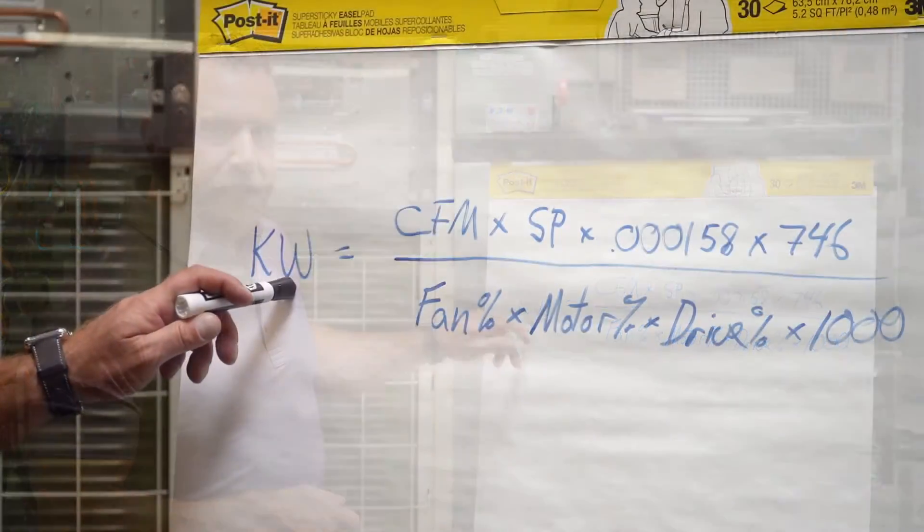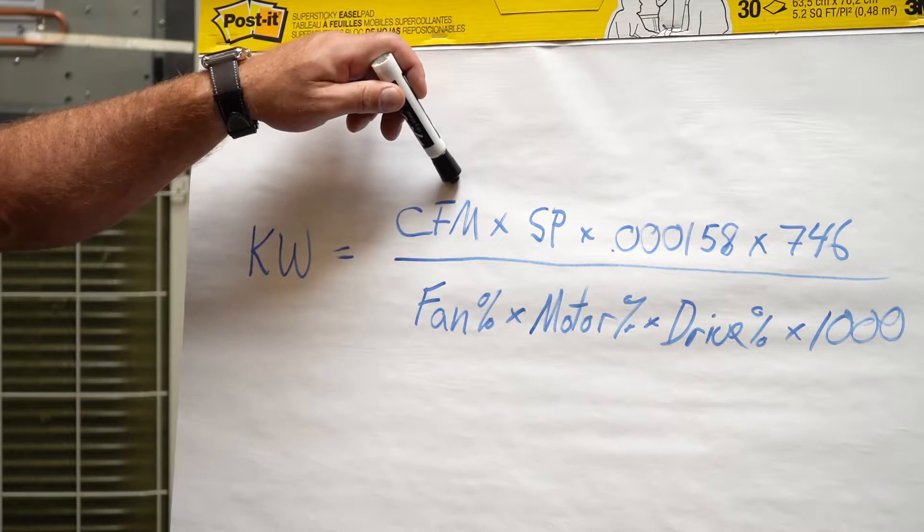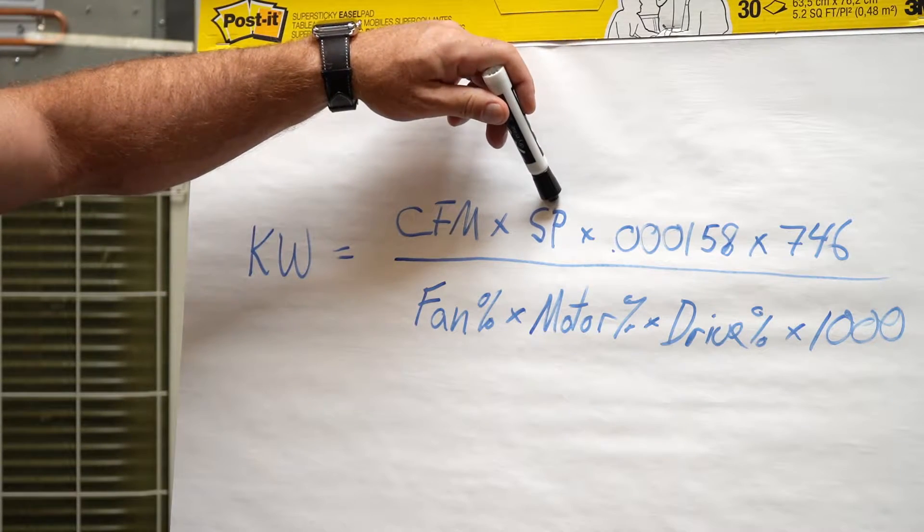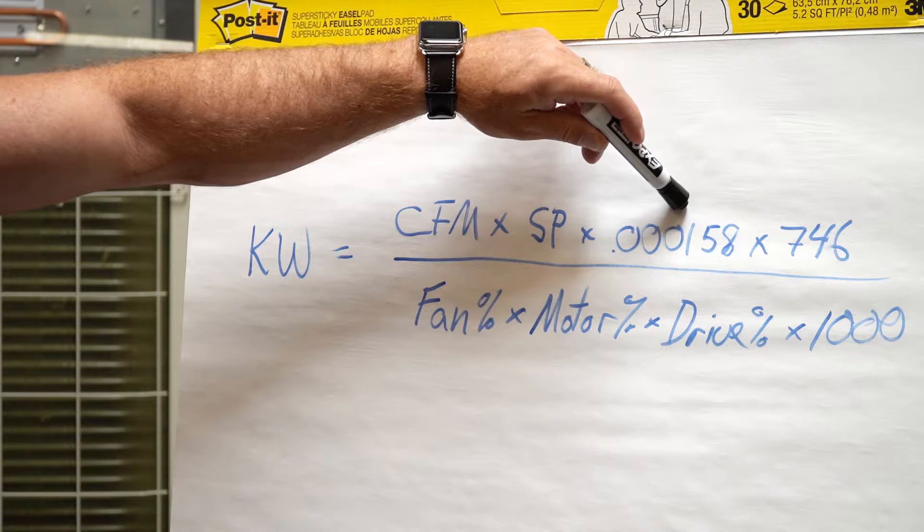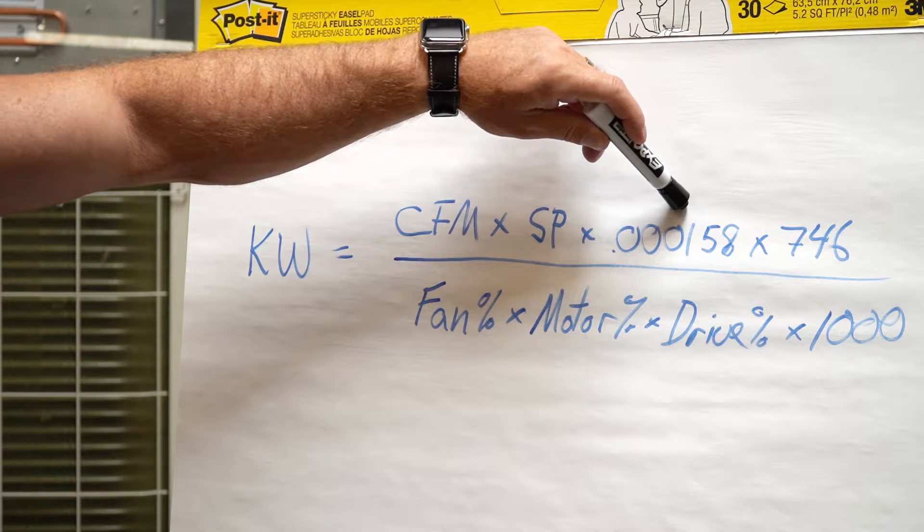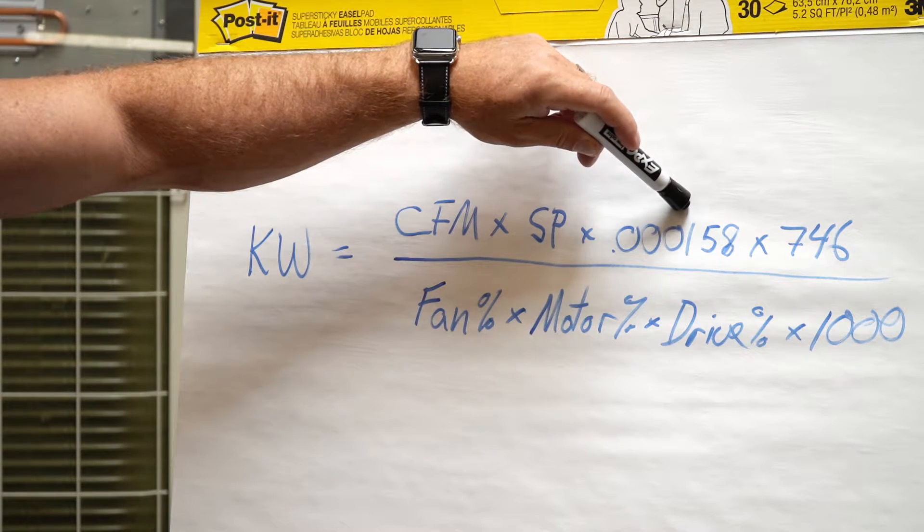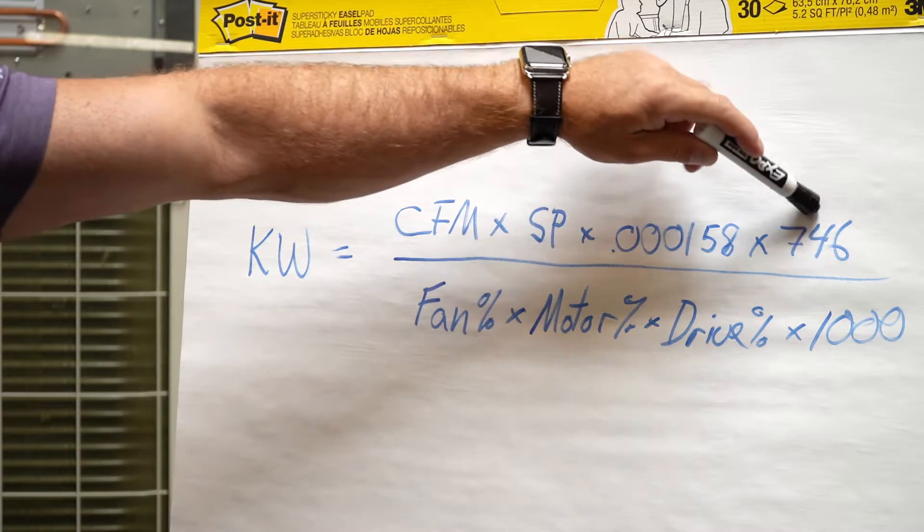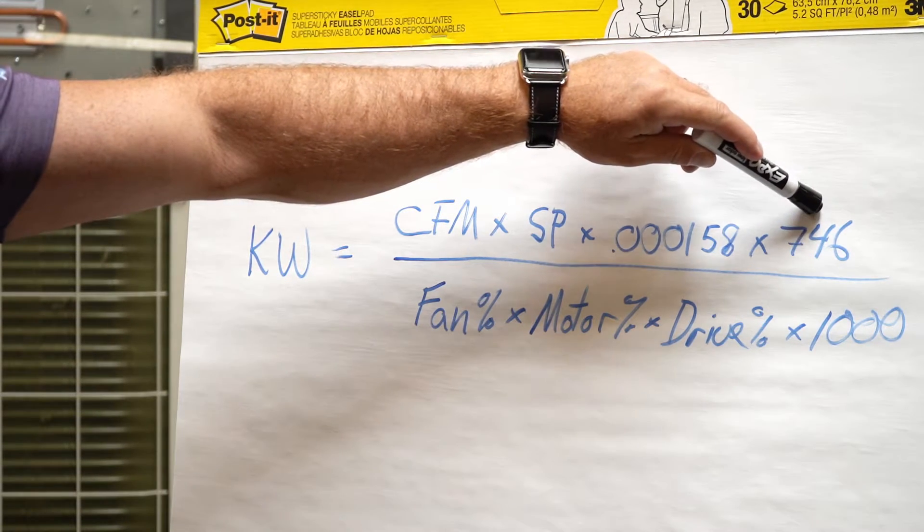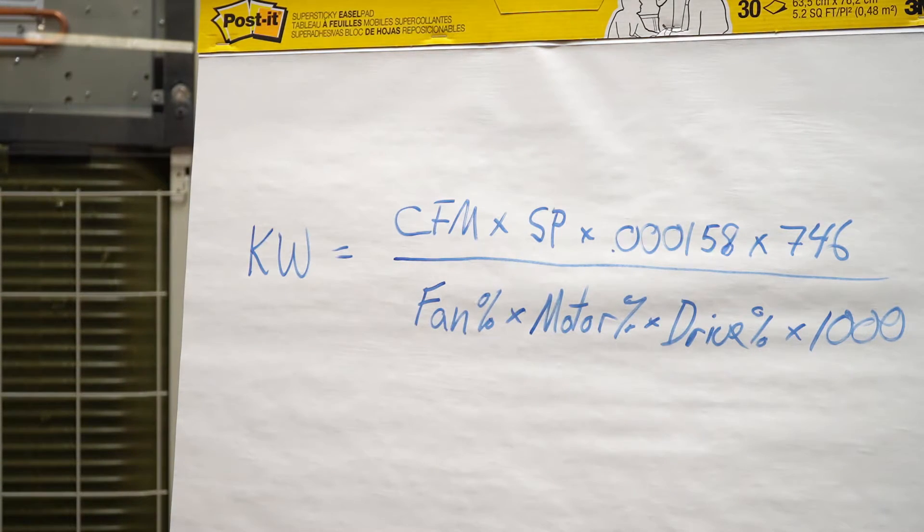This equation is currently set up to calculate KW, so we're going to take our airflow in CFM multiplied by our system static pressure multiplied by .000158, which is our conversion factor for standard temperature and pressure, times 746. And the 746 component is our conversion factor between horsepower and KW.